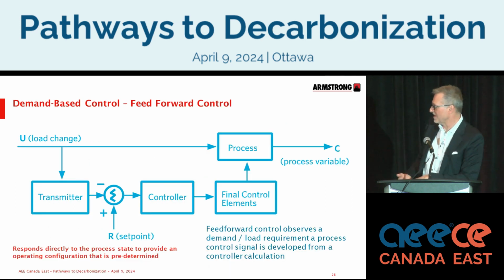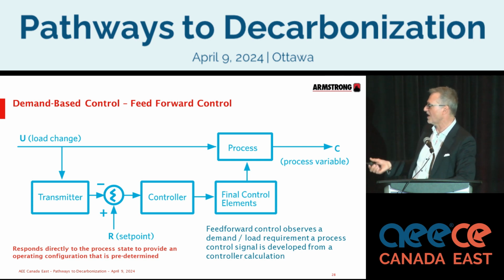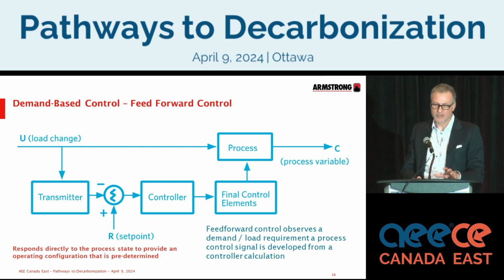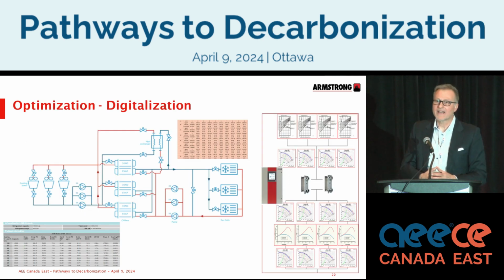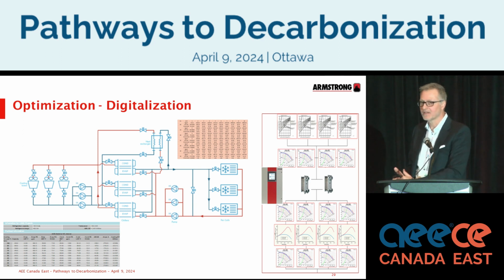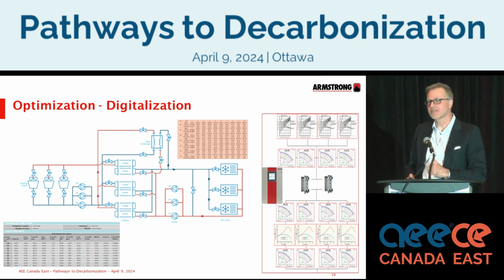So what is demand-based controls? Well, it responds directly to the process state to provide an operating configuration that is predetermined. So based on the indoor load and the outdoor conditions, we have already predetermined where to operate the equipment based on that situation. And this is based on a feed-forward control or demand logic requirement. So basically, from the load and the ambient conditions, we now have maps on the pieces of equipment. Because we have those maps and we have the efficiencies associated with those pieces of equipment, we will know how to stage them at their best efficiency points. So optimization is just digitalization. We have the digital maps.